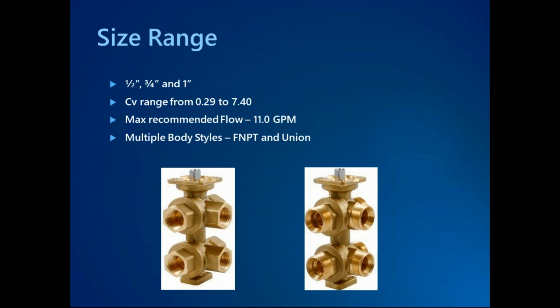When it comes to the size range for 6-ways on the market today, these are designed primarily for low flow applications. Most manufacturers out there only offer 1/2 and 3/4 inch, with a few making a 1-inch solution as well. Similar with the CV range and the max flow, a lot of manufacturers typically max out around a 4.5 CV, which correlates roughly to a 7 to 7.5 GPM flow, with a few manufacturers going above that. But for the most part, we're designing these for a single room. So a single chilled beam would be feeding a single classroom or a single office space or a single conference room, stuff like that, as opposed to trying to zone together very large spaces as you may have done with fan coils or VAVs.